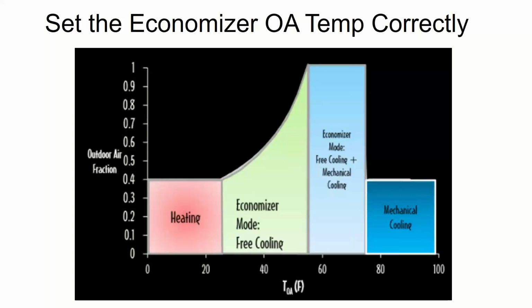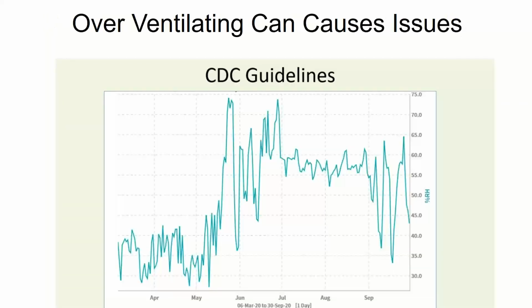The next recommendation was, why don't you try bringing in a bit more, instead of 20% outside air, maybe 30%. That's okay if your system can handle it, and some can and some can't. But the more outside air you bring in, the more challenging it becomes to control humidity. Both ASHRAE and the CDC have at various times over the past 12 months recommended bringing in more fresh air, and that's okay, just make sure your HVAC engineer confirms your system can handle it. Many cannot. Systems should handle the code required ventilation air, but bringing in extra air is going to be a challenge.